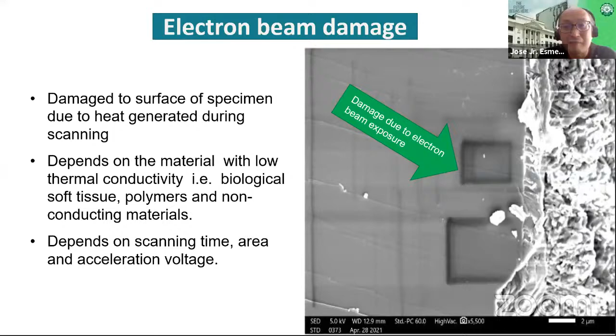So in a scanning electron microscope, especially for very sensitive materials, from the perspective of the ones being sampled, it's very important to know whether the sample is destructive or not, and also whether the sample is non-conductive or conductive. This is where we apply coating. Sometimes those asking for analysis will say the sample is conductive, but in a way it's not really. Even carbon samples are conductive in a linear way, but the surface resistivity is still very high, about 1 megaohm. So for that kind of material, it's still important to coat it with metal in order to mitigate sample charge-up or image distortion.